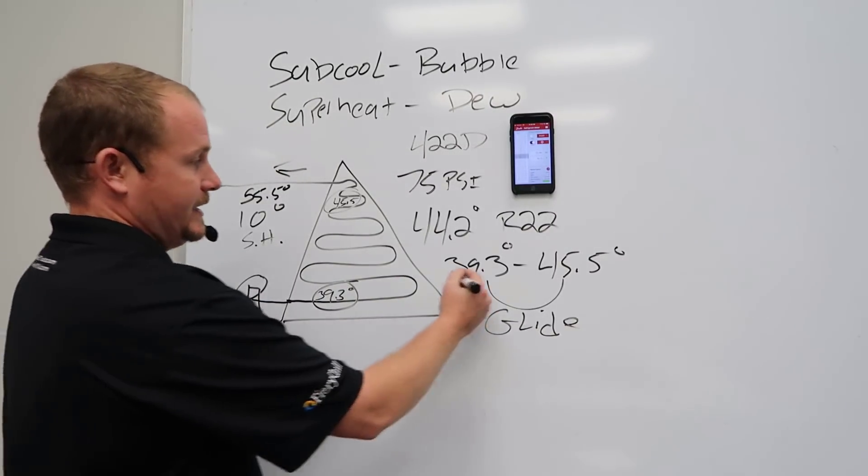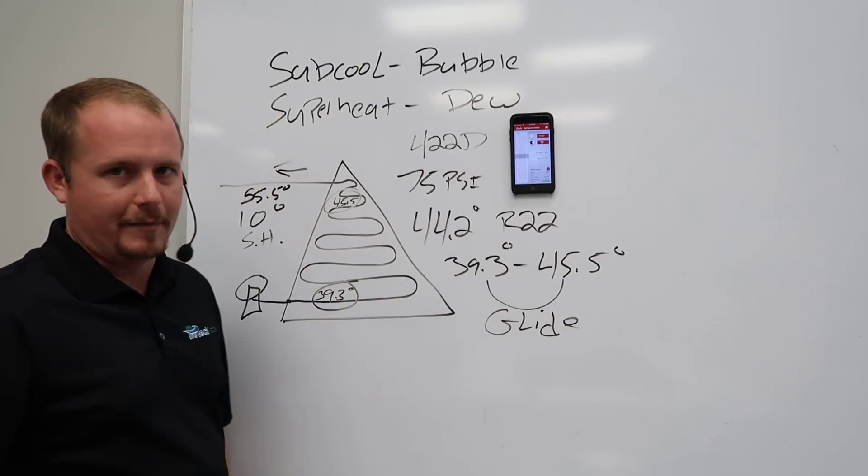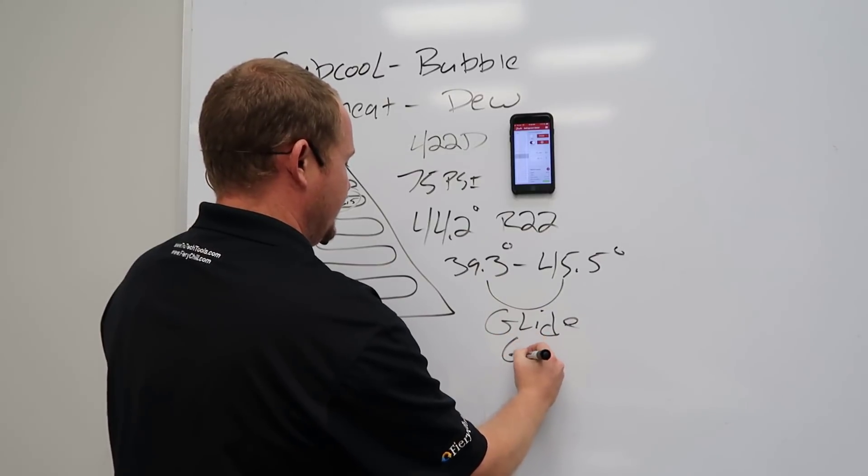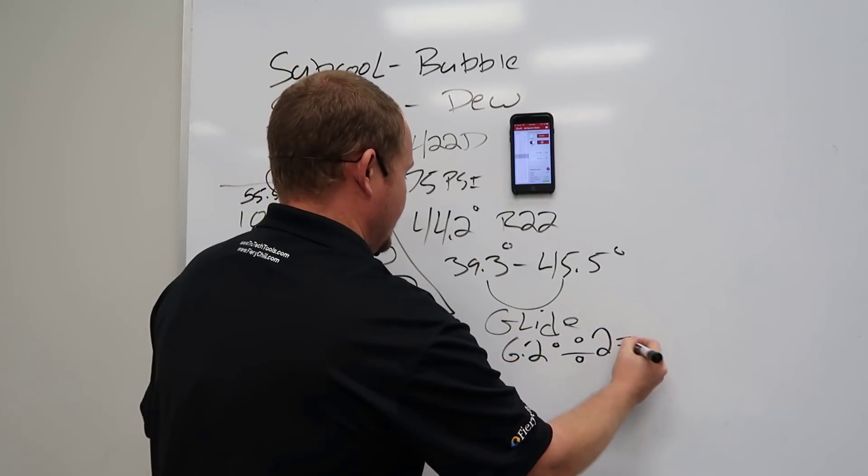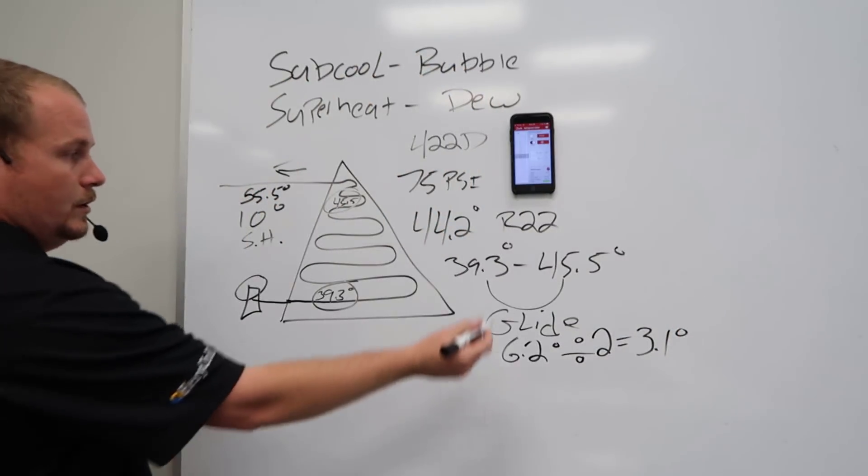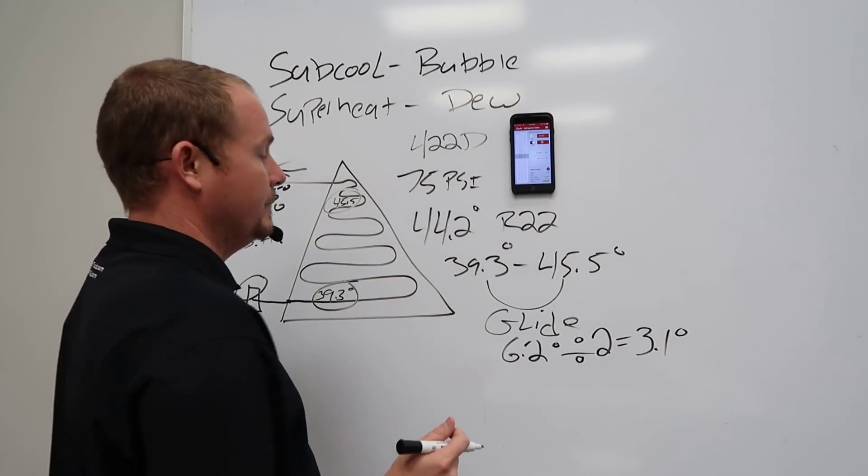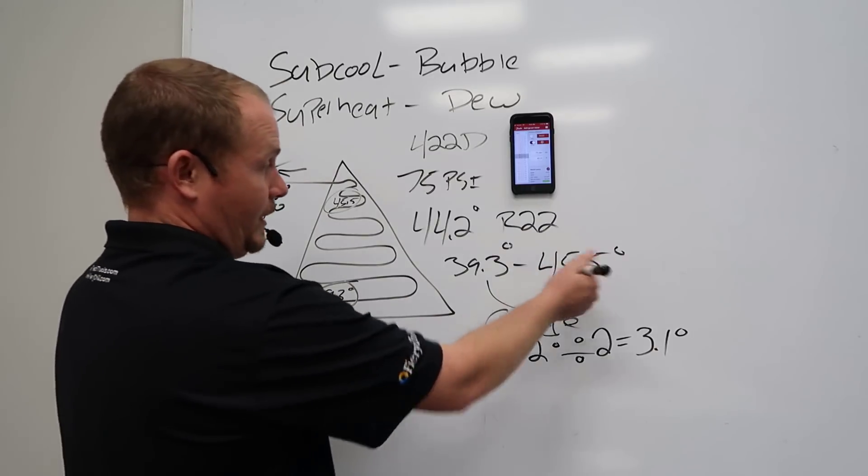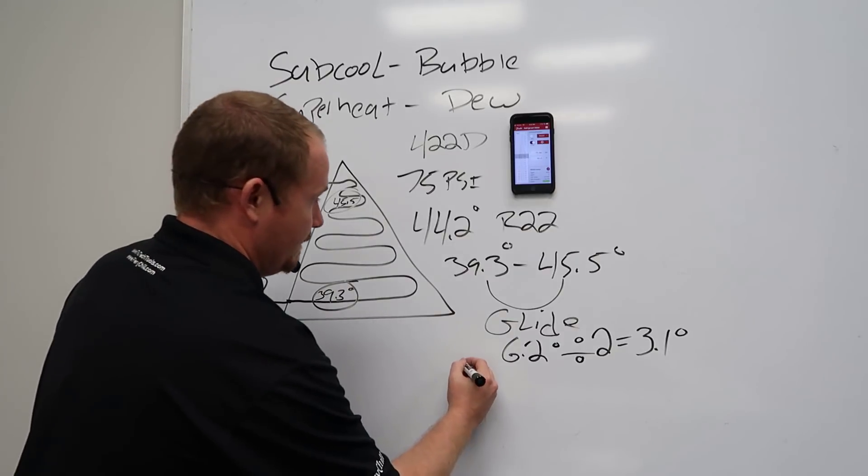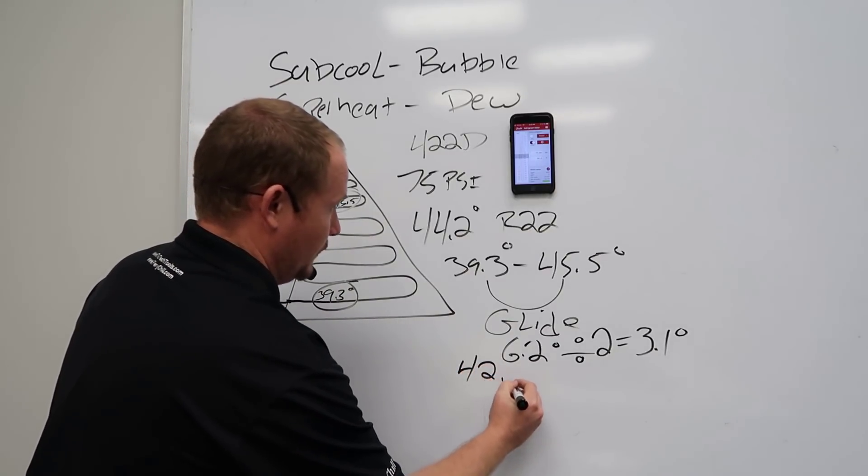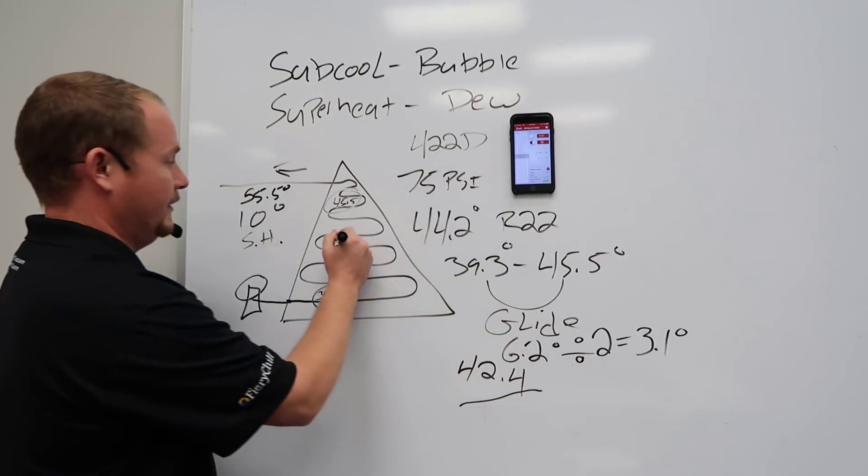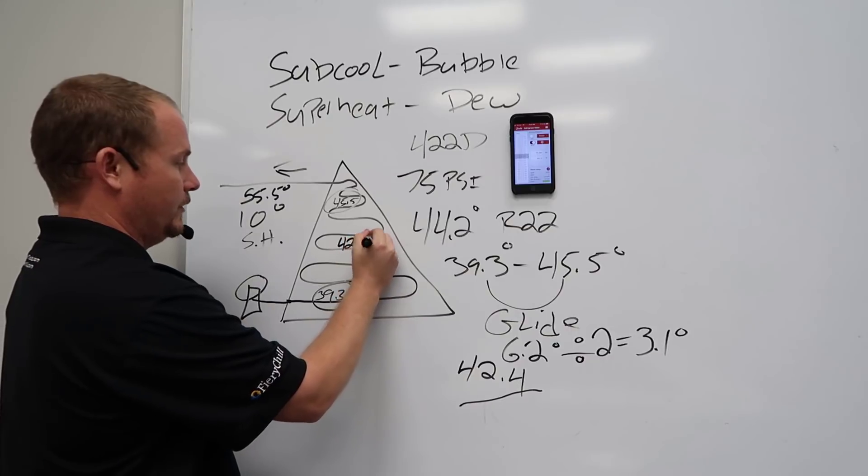What we do is we just take these two points, and I'm just going to do rough math here. We're going to say that it's 6.2 degrees of glide divided by 2 equals 3.1 degrees. So we take 39.3, we add 3.1 degrees, or we subtract 3.1 degrees from 45.5, and we come up with 42.4, and that 42.4 is now our average evaporator temperature, 42.4 degrees.